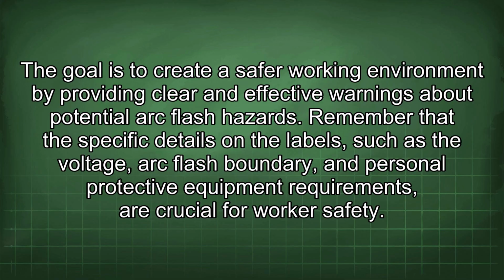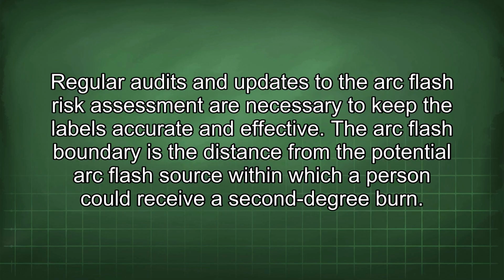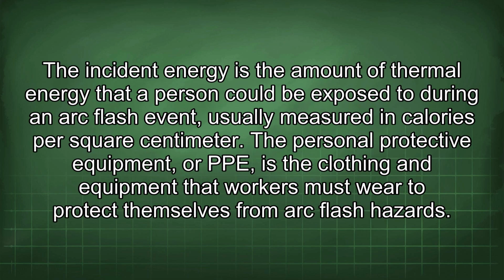Remember that the specific details on the labels, such as the voltage, arc flash boundary, and personal protective equipment requirements, are crucial for worker safety. Regular audits and updates to the arc flash risk assessment are necessary to keep the labels accurate and effective. The arc flash boundary is the distance from the potential arc flash source within which a person could receive a second-degree burn. The incident energy is the amount of thermal energy that a person could be exposed to during an arc flash event, usually measured in calories per square centimeter.